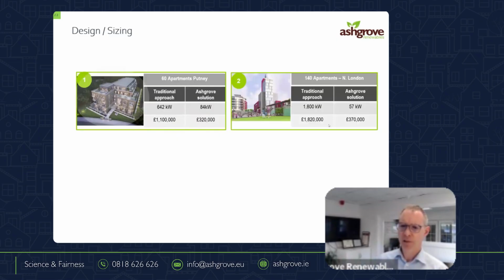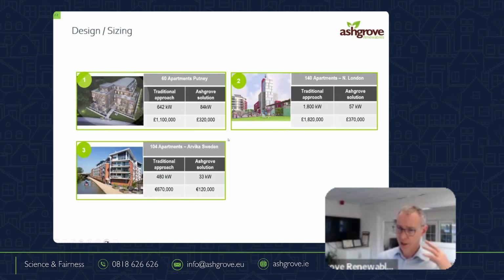We see similar examples of this all over the place, right? A lot of these big projects we did were in London, by the way. 140 apartments, 1,800 kilowatts. This was for hot water. 57 kilowatts was actually what's needed here, right? Now it needs to run 24 hours a day, but over 24 hours it can produce the required amount of energy. So it requires a different mindset.